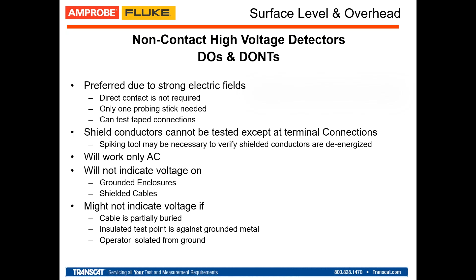the soil, or anything that is concrete or standing above the underground cable, might block the expansion or the propagation of the electromagnetic field. Hence the reason why you're going to see very, very few situations where someone uses an NCV to detect voltage on an underground cable. The equipment is just not powerful enough to detect the signal, and the layer above the cable is blocking the electromagnetic field. And that's the reason why we also have underground utility locators, which we'll talk about later.